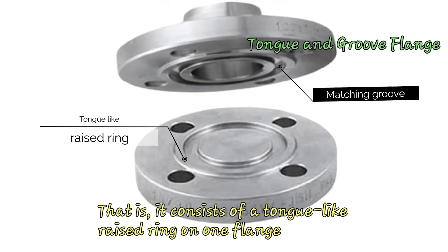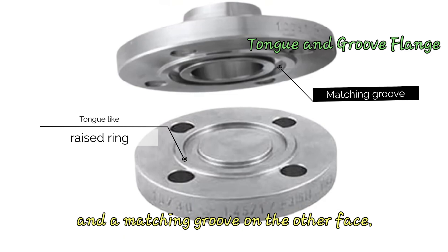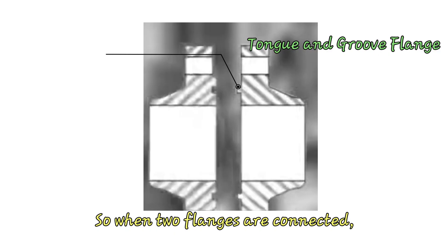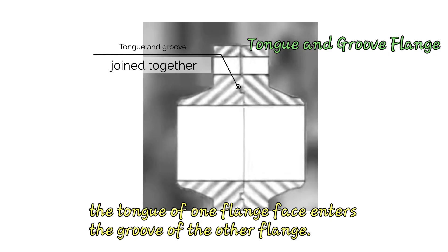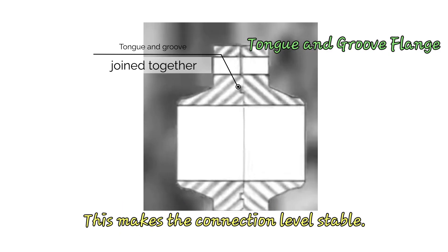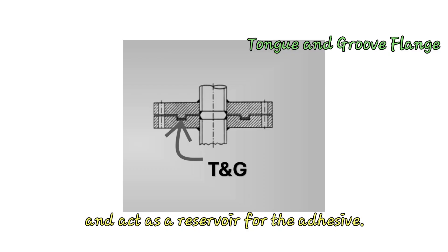The tongue and groove flange features matching grooves and raised sections — it consists of a tongue-like raised ring on one flange and a matching groove on the other face. When two flanges are connected, the tongue of one flange face enters the groove of the other. The advantage of tongue and groove is that it self-aligns, acts as a reservoir for adhesive, and can be attached to the pipe without welding.